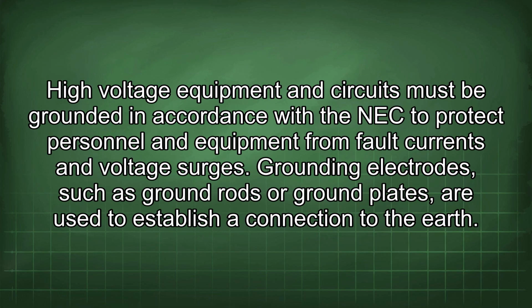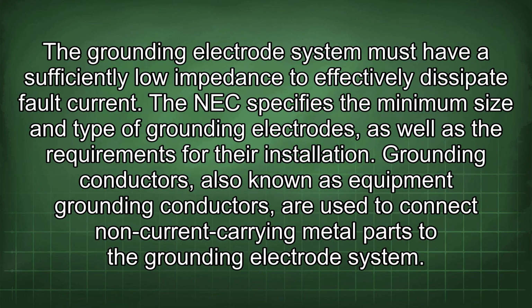High voltage equipment and circuits must be grounded in accordance with the NEC to protect personnel and equipment from fault currents and voltage surges. Grounding electrodes, such as ground rods or ground plates, are used to establish a connection to the earth. The grounding electrode system must have a sufficiently low impedance to effectively dissipate fault current. The NEC specifies the minimum size and type of grounding electrodes, as well as the requirements for their installation.